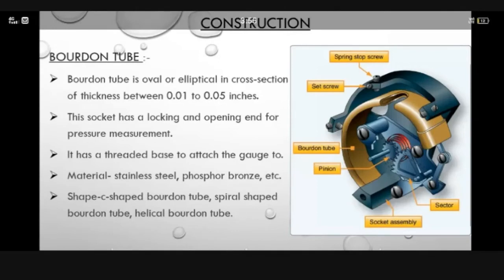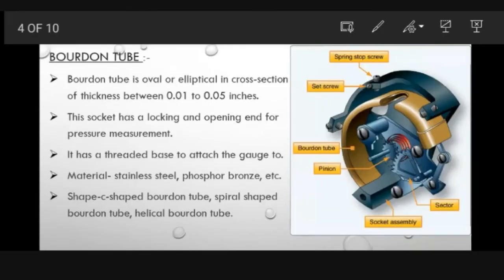Over to you, Tejal. I will be explaining the construction and the working of the Bourdon tube pressure gauge. The main parts of the Bourdon tube pressure gauge are the Bourdon tube, sector and pinion, and dial and pointer. The Bourdon tube is the main part of the gauge, and it is a transducer. It converts the applied pressure into a signal. This tube is fixed and open at one end to receive the pressure which is to be measured, and its other end is free and closed. The cross section of the Bourdon tube is elliptical, and the tube is in a bent form which looks like a circular arc. Its thickness is 0.01 to 0.05 inches. They are found in C shape and helical shape.